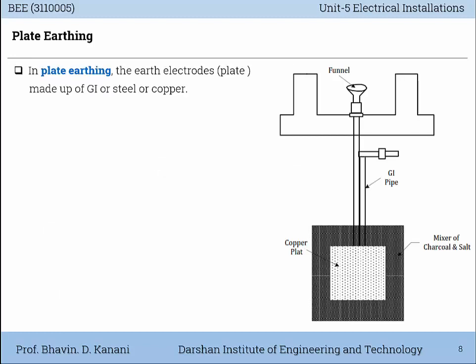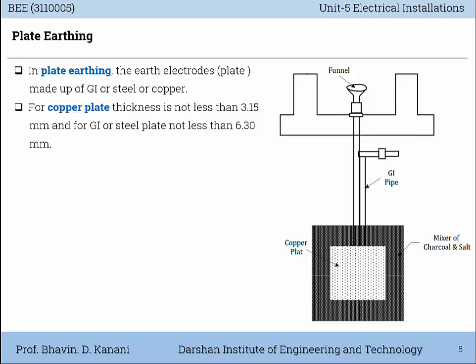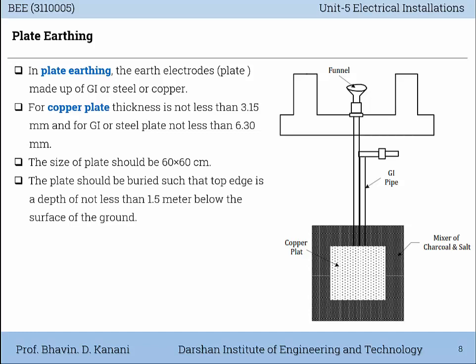Next is plate earthing. You can refer to this figure. In plate earthing, the earth electrode, that means the plate, is made up of galvanized iron (GI), steel or copper. For a copper plate, the thickness is not less than 3.15 mm, and for a GI or steel plate it is not less than 6.30 mm. The size of the plate should be 60 by 60 centimeters. The plate should be buried such that its top edge is at a depth of not less than 1.5 meters below the surface of the ground.